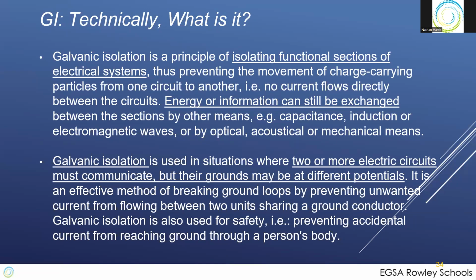And where could that be? It could be static. It could be ground loops. It could be the result of induced voltages into systems. But you want to isolate these systems from each other. So when you're in the process of creating, developing, specifying, and starting up a control system, we have to be very careful about galvanic isolation. We make light of it because it all came from a bunch of frogs, but it's really important to isolate these two circuits from each other.